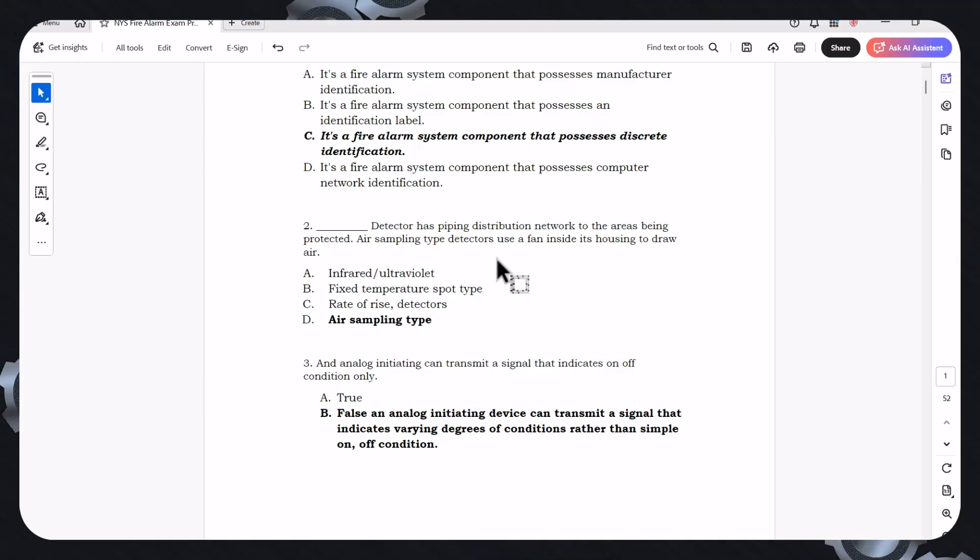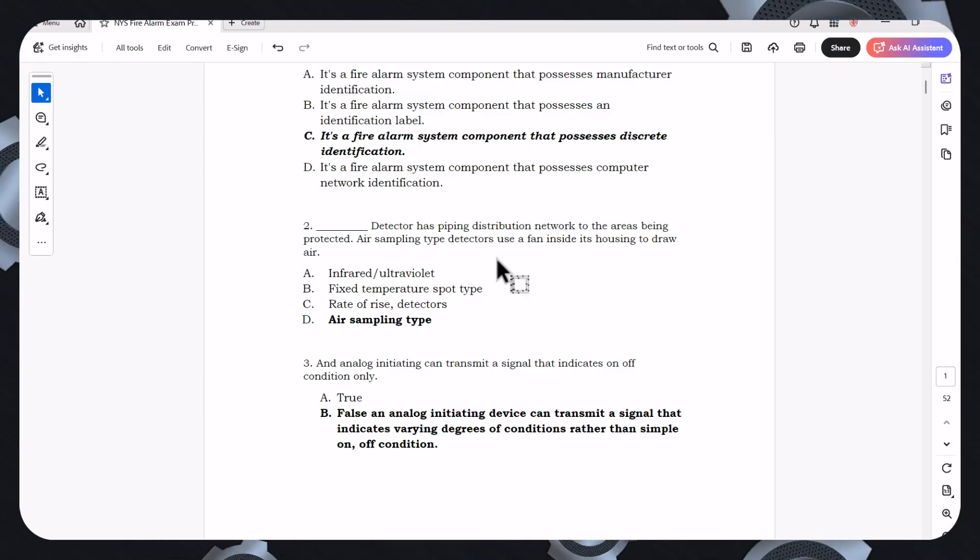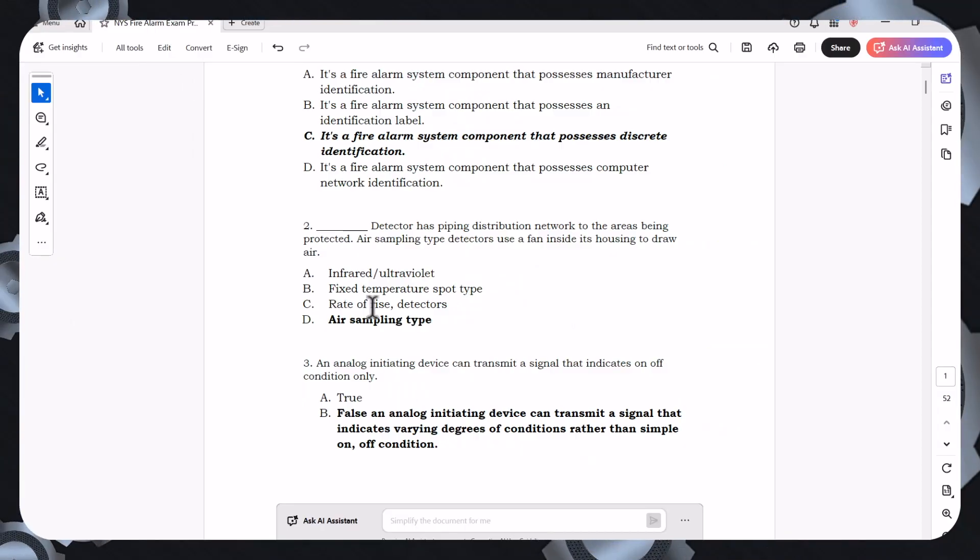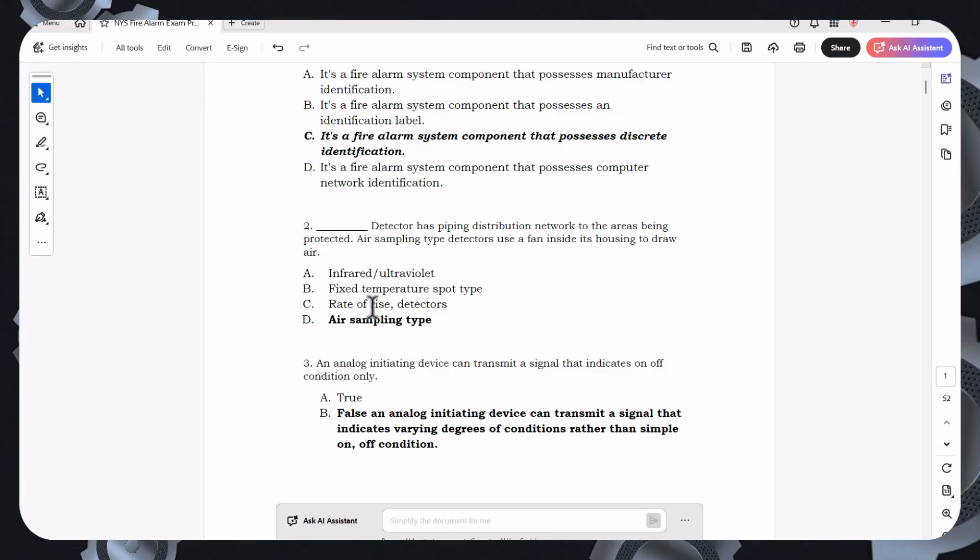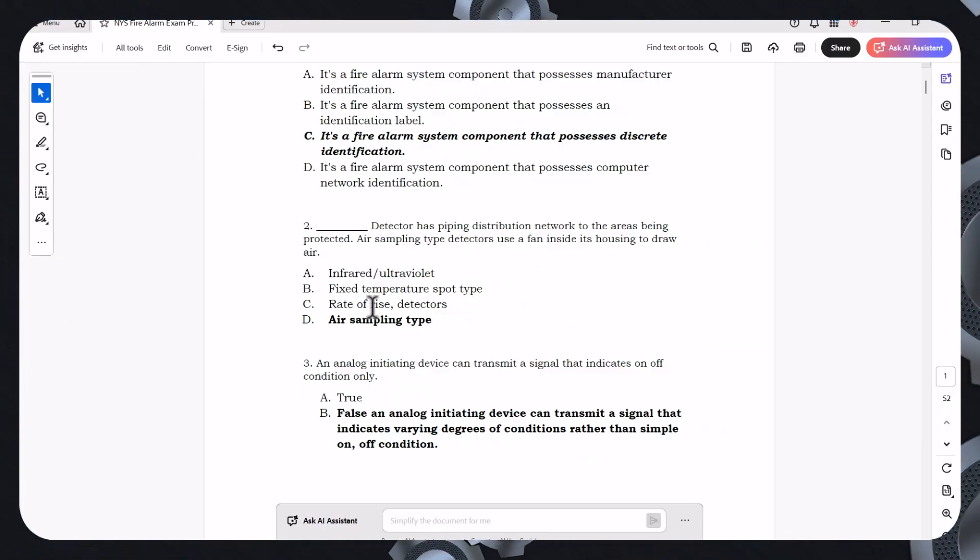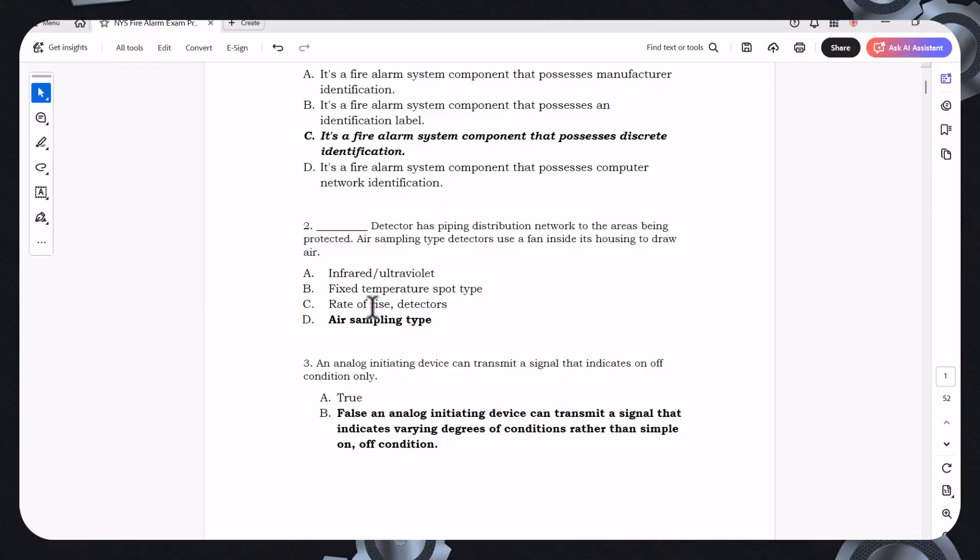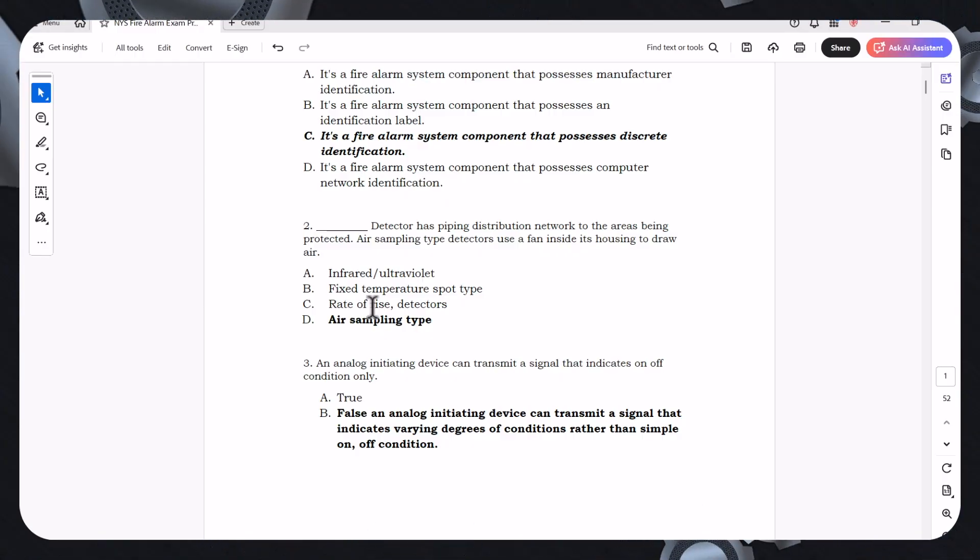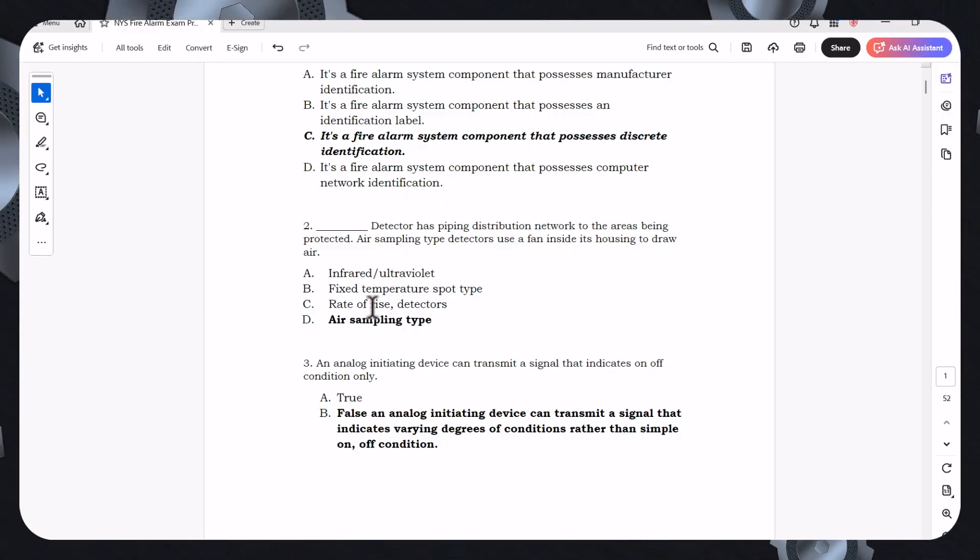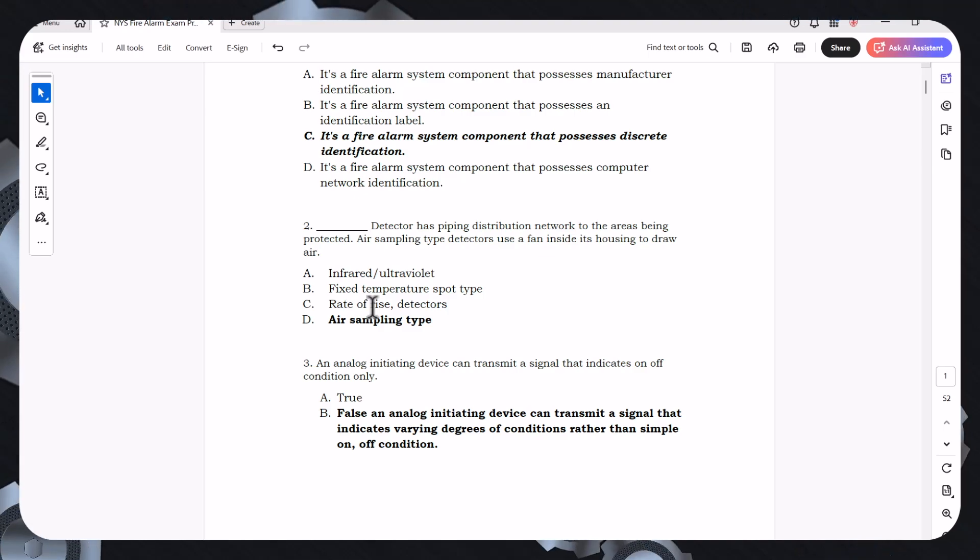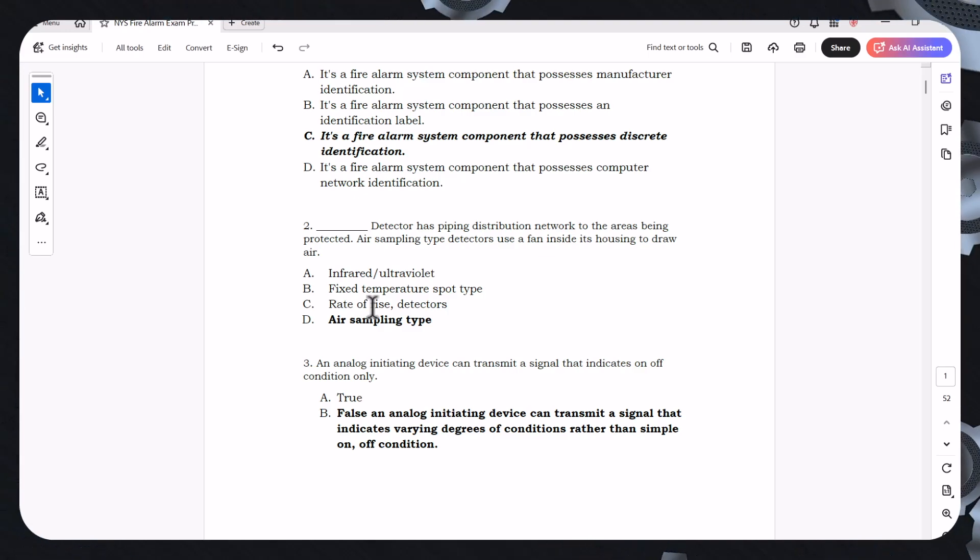Now the last question I'm going to go over so I can let you go and actually absorb all this information so you can pass your test. An analog initiating device can transmit a signal that indicates on and off conditions only. Is that a true or false? The answer for this is false. An analog initiating device can only transmit a signal that indicates varying degrees of conditions rather than a simple on-off condition.